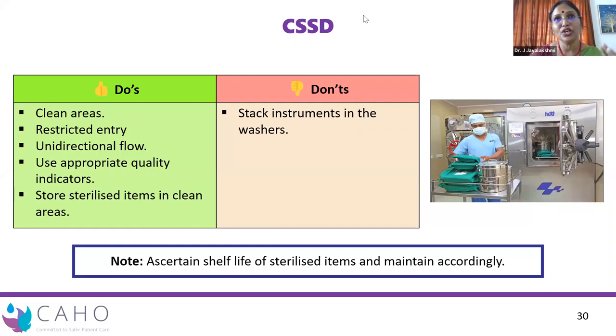So it is important that you document your entire activity. If you have more than one sterilizer, you need to know which day, which batch, which sterilizer the material was sterilized in, and what went into it. This matters because if any one instrument fails, or shows no color change in the chemical indicator, or if using an older biological indicator method you find a day later it hasn't passed, you have to recall all the instruments. So proper documentation of everything is important.